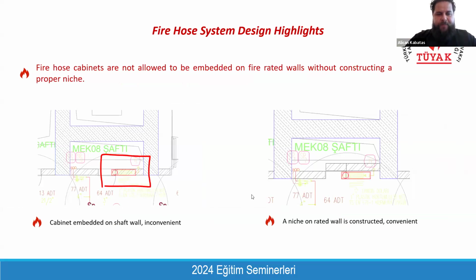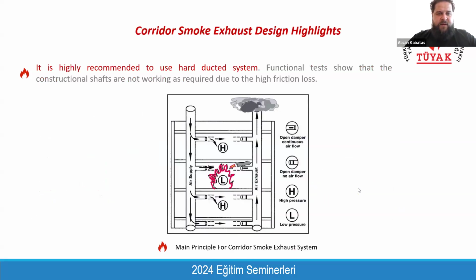And these embedded flush type fire hose cabinets are not allowed to be located within the fire rated wall, because when you embed this kind of material into the fire rated wall, the main thickness of the wall will be gone, and the thickness of the wall is creating this fire rating. That's why, if you would like to locate your fire hose cabinets onto a fire rated wall and use embedded or flush type hose cabinets, then you need to design your wall construction with a convenient niche on it. Owing to this niche, without damaging the wall, you can locate your fire hose cabinet, and it can look like an embedded flush type cabinet from an architectural point of view.